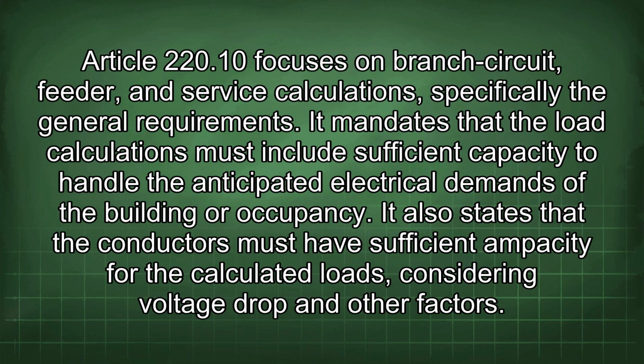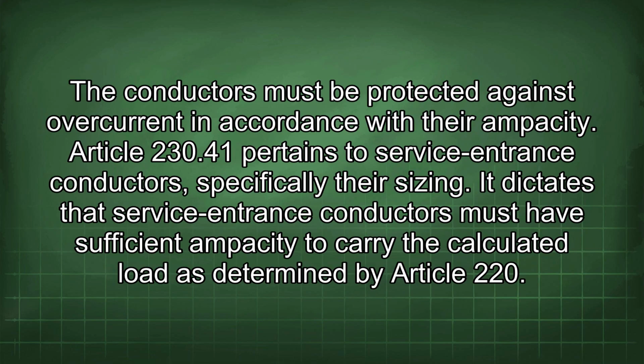Article 220.10 focuses on branch circuit, feeder, and service calculations, specifically the general requirements. It mandates that the load calculations must include sufficient capacity to handle the anticipated electrical demands of the building or occupancy. It also states that the conductors must have sufficient ampacity for the calculated loads, considering voltage drop and other factors. The conductors must be protected against overcurrent in accordance with their ampacity.